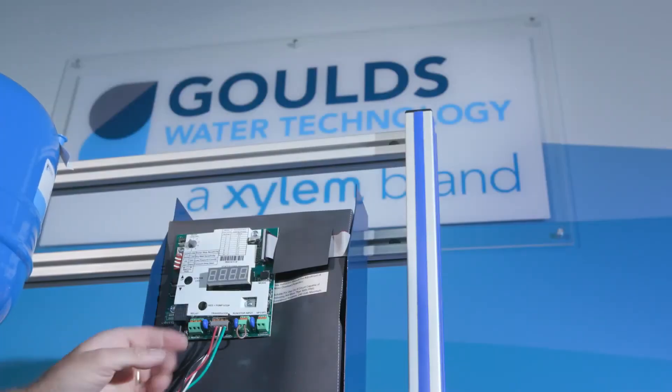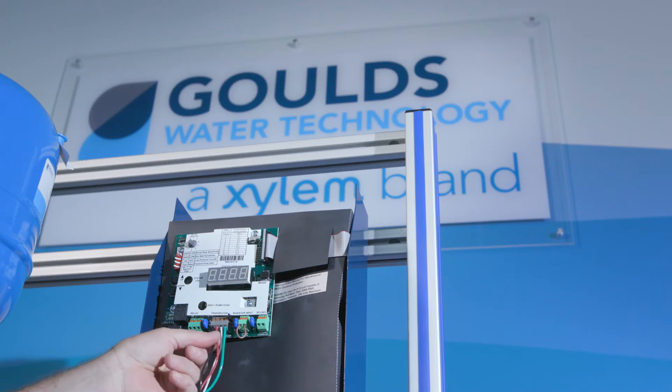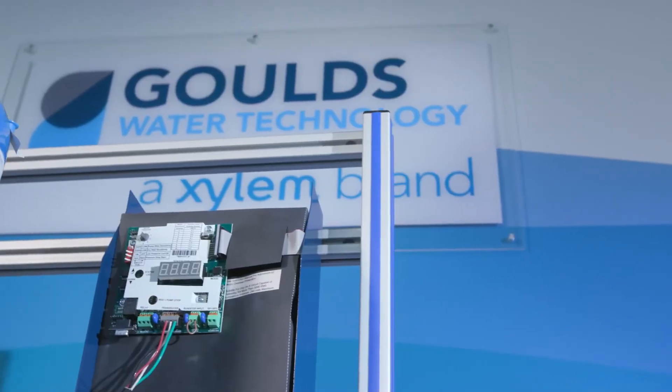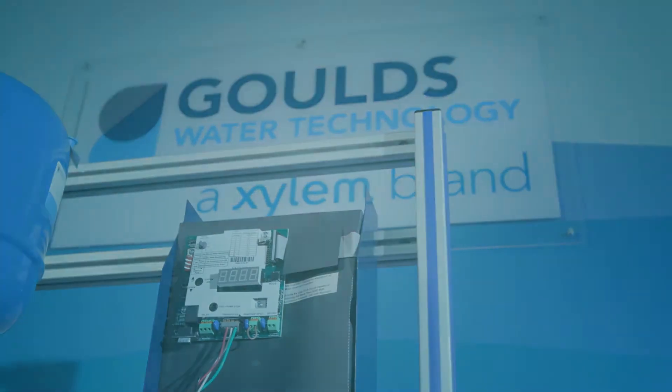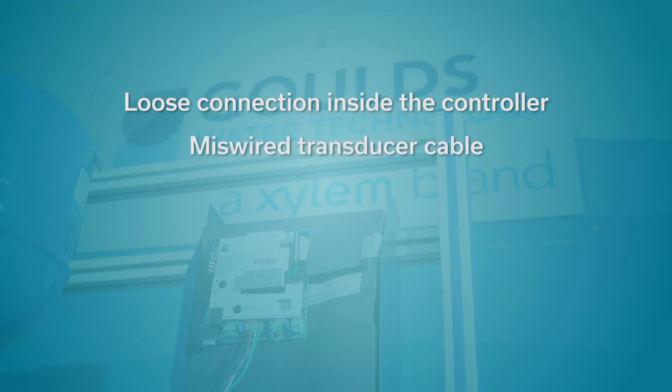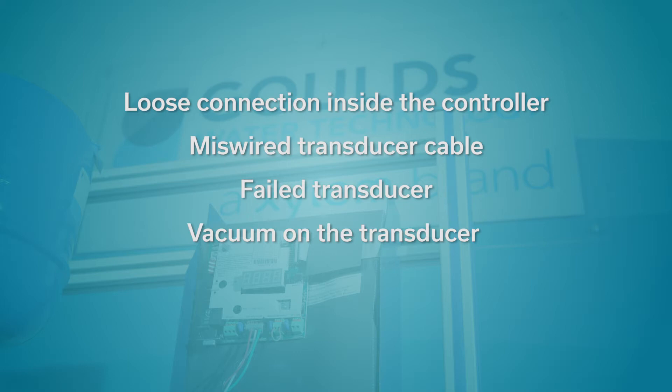First, we'll begin with the pressure transducer used on residential VFDs such as the SOLO2. Much of this information is in the installation manual IM260. We will check the following possible issues: loose connection inside the controller, miswired transducer cable, failed transducer, vacuum on the transducer, or a bad user interface board.